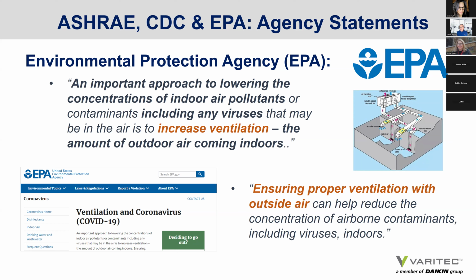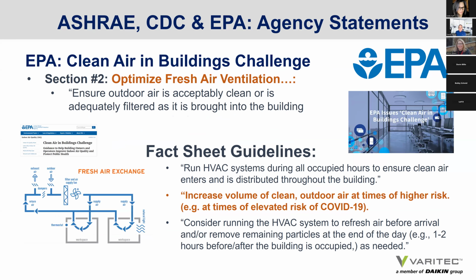Now, let's be cautious, because the EPA's understanding of ventilation air is outside air. That is not ASHRAE Standard 62.1's definition of ventilation air to the zone, which is a combination of outside air and properly treated return air. So when the EPA says ventilation air, they're talking about outside air. And it goes on to say that ensuring proper ventilation with outside air can help reduce the concentration of airborne contaminants and, of course, viruses indoors.